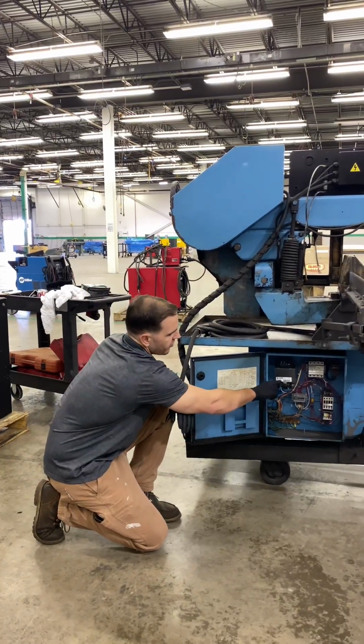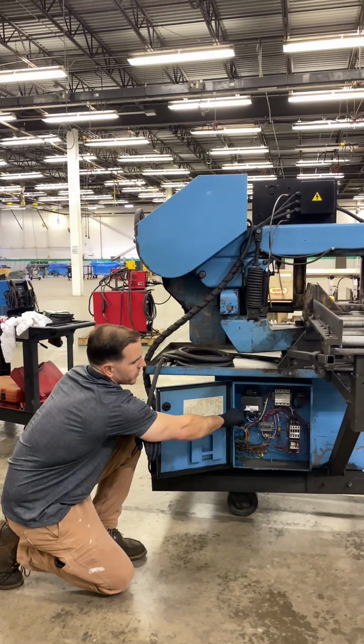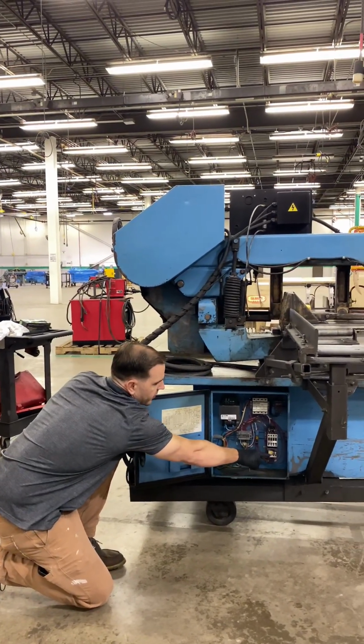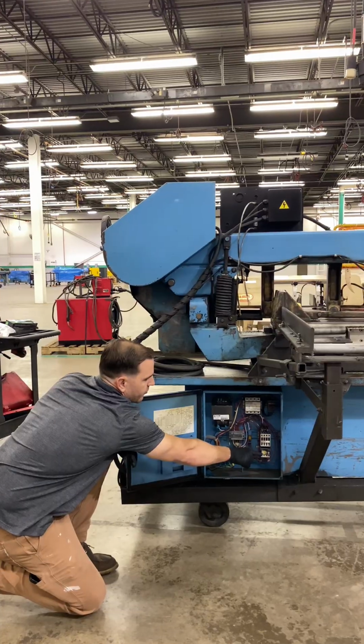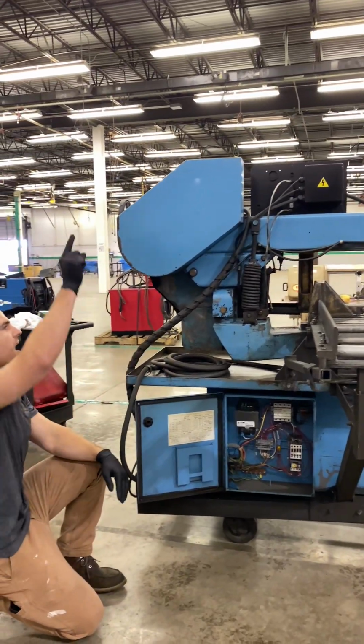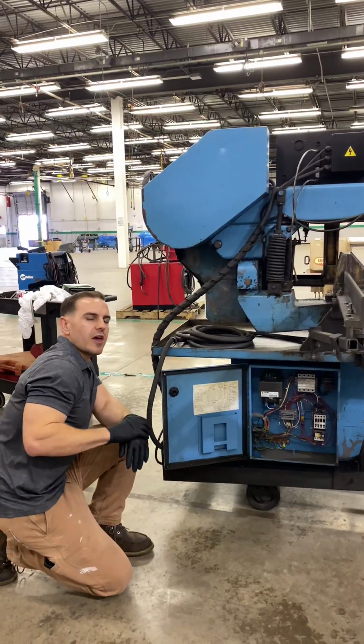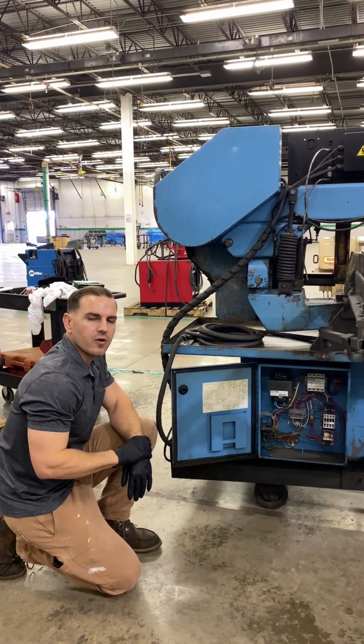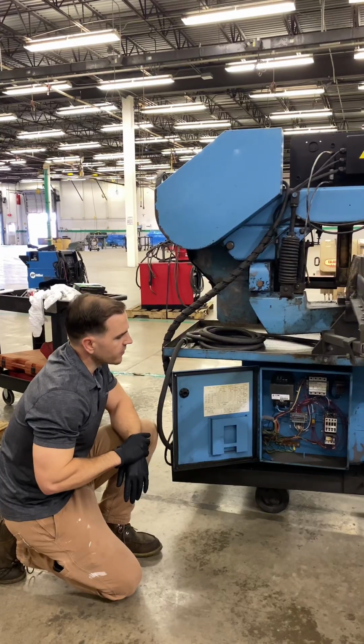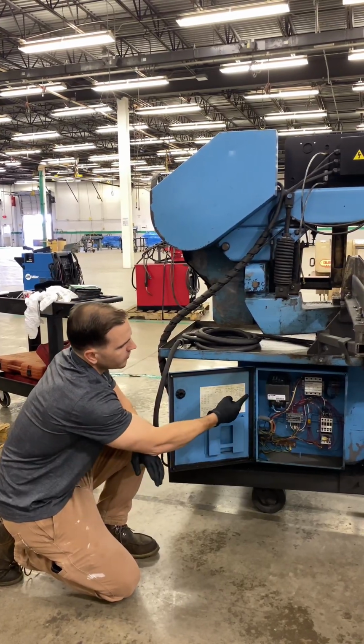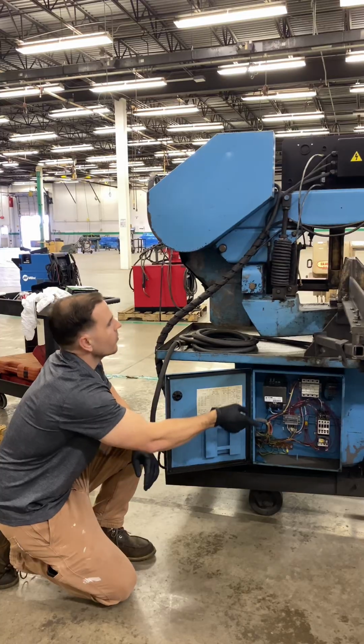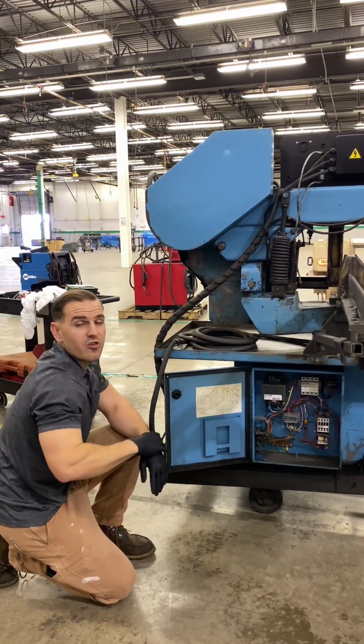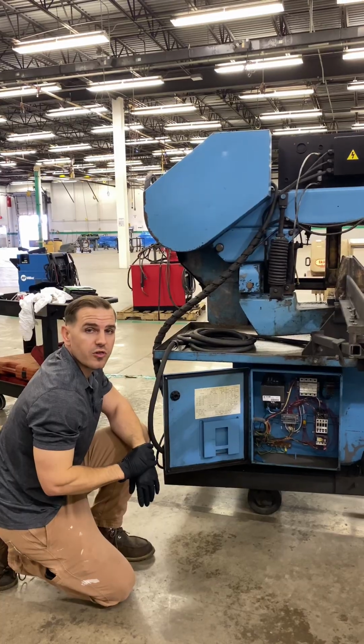One is changing the voltage on your transformer. Two is adjusting your overload to the correct amperage. And three, on the back side of the machine, we're going to be changing the motor taps to allow for high or low voltage. Today, in this case, we're wired for a 230 volt machine all the way through to the motor, and we're going to be changing this to a 480 volt machine, and I'm going to show you how.